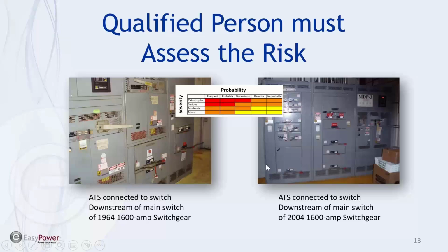Well, at first glance that may be the case, but then you start looking into it a little bit deeper, and you find out that this one has an arc flash label and tells you what it is. That's one good thing. And it also has maintenance labels, one after another, kind of stacked up onto the switchgear, so you know it's been maintained on a pretty regular basis. This one, the 2004 switchgear, has no stickers. So you contact the facility manager and you say, how long since you did maintenance on this? Well, Lee, we haven't been very good about that. I said, well, give me a time frame, just a general idea. Well, I don't think we ever have. So it's now been 18 years since that's been maintained.